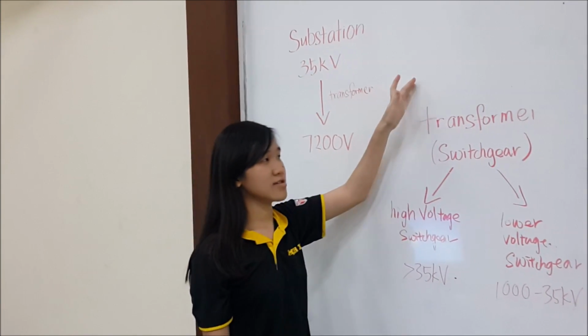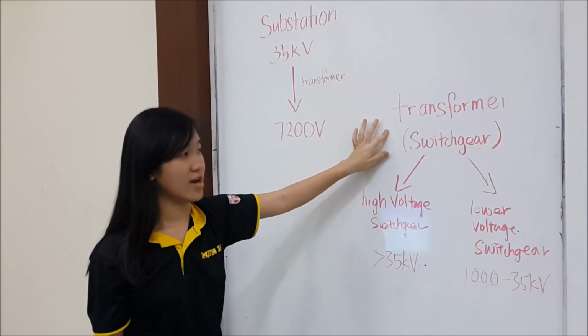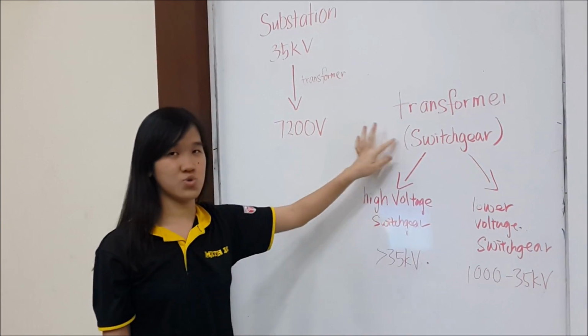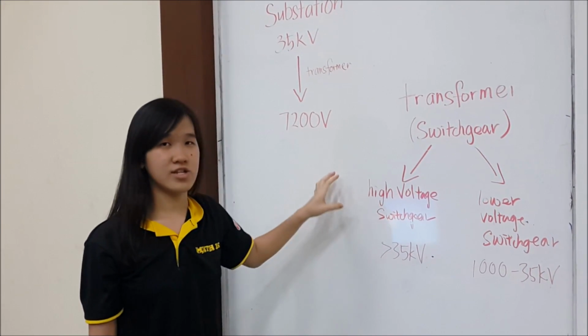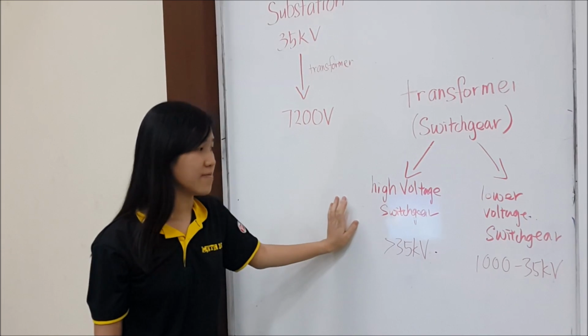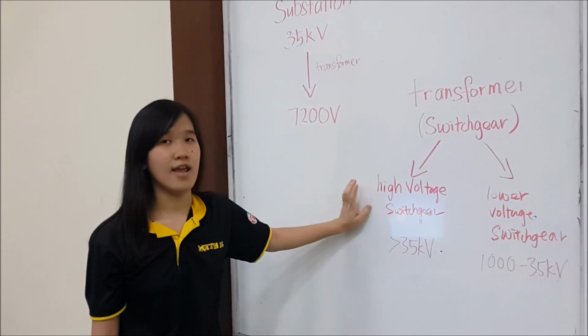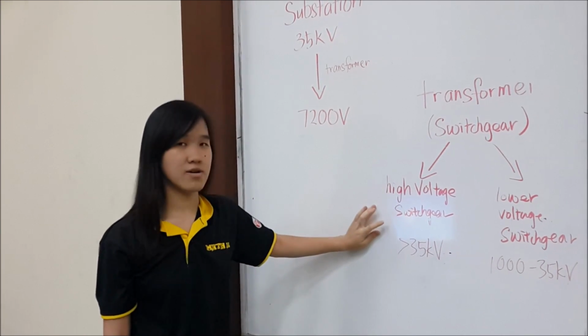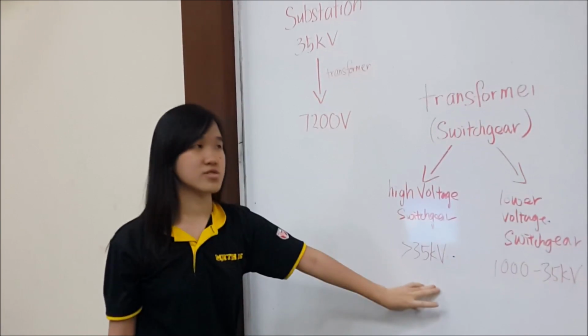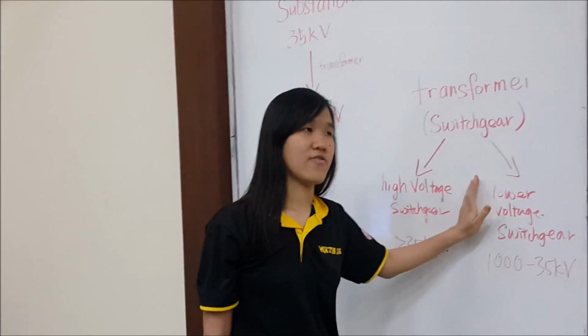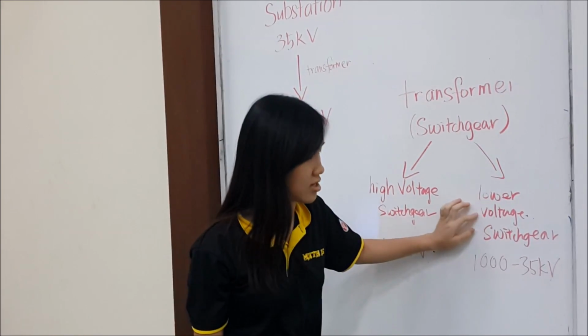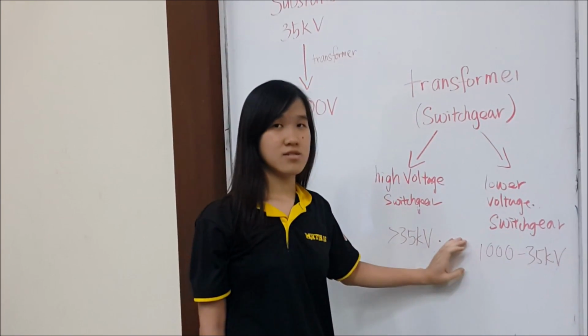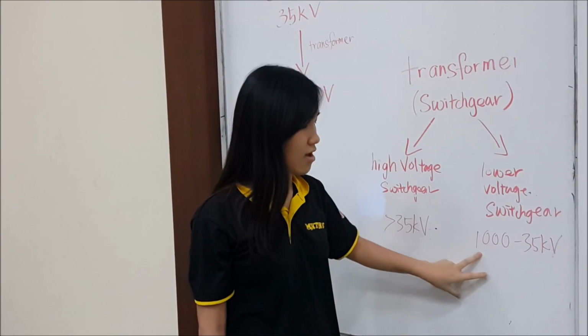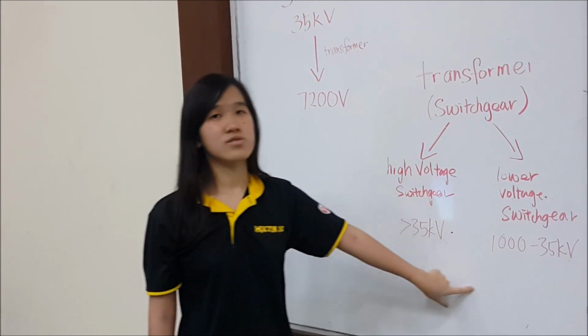In the transformer, there's a safety device called switchgear. At the high voltage side of the transformer, there is high voltage switchgear that can handle power above 35 kilovolts. At the other end of the transformer is the lower voltage switchgear, which can handle voltage of 1000 to 35 kilovolts.